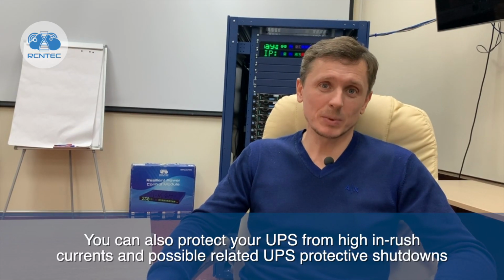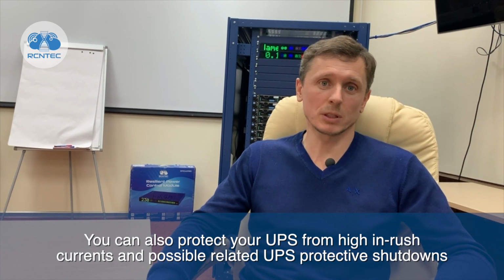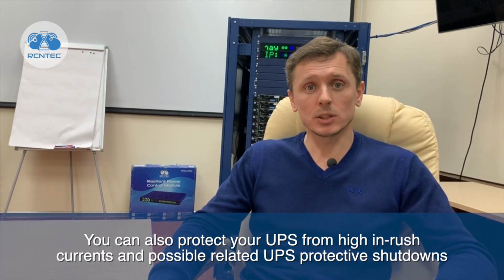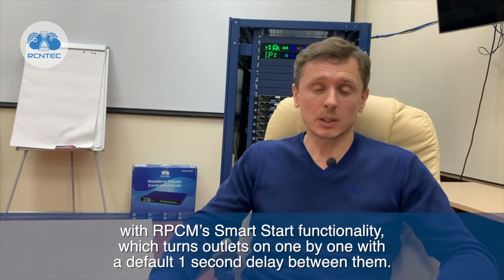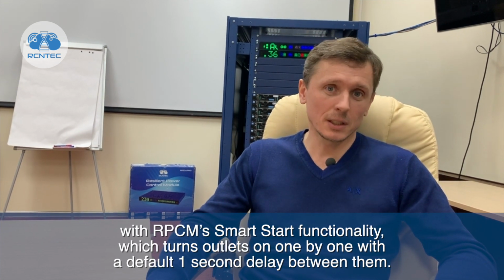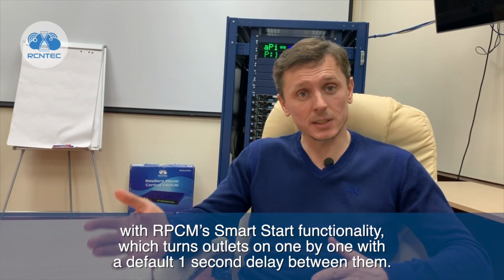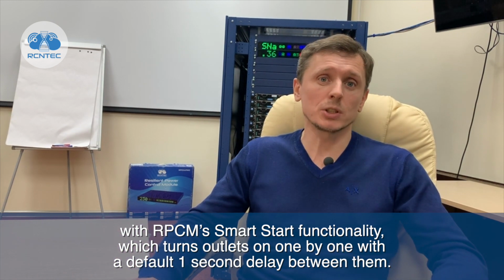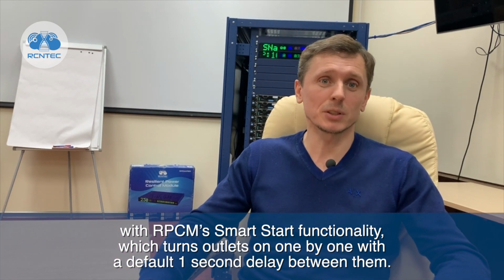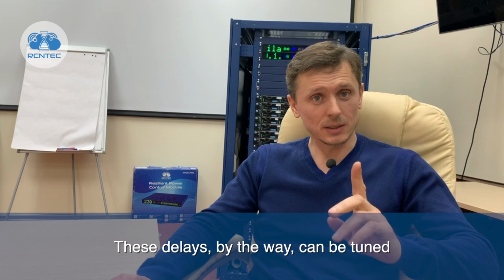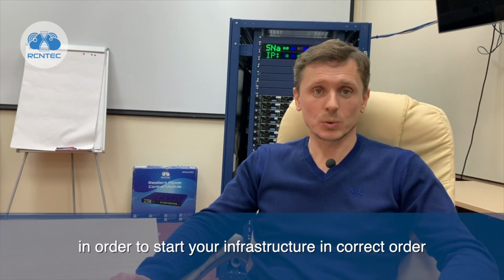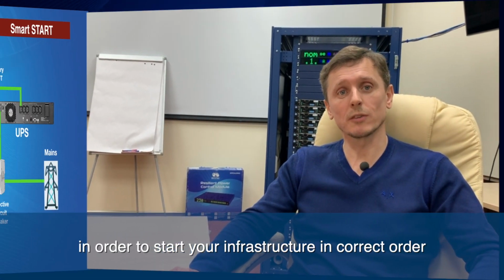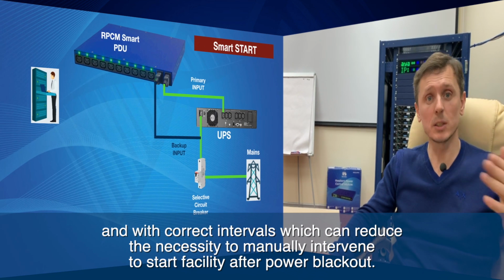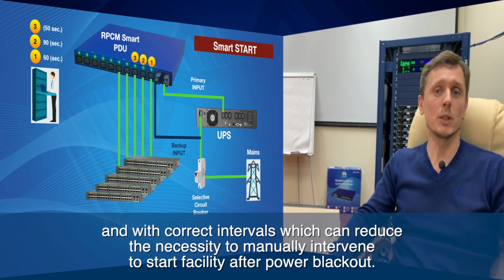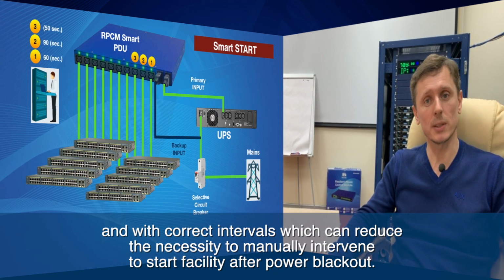You can also protect your UPS from high inrush currents and possible related UPS protective shutdowns with RPCM's Smart Start functionality, which turns outlets on one by one with a default 1-second delay between them. These delays, by the way, can be tuned in order to start your infrastructure in correct order and with correct intervals, which can reduce the necessity to manually intervene to start the facility after a power blackout.